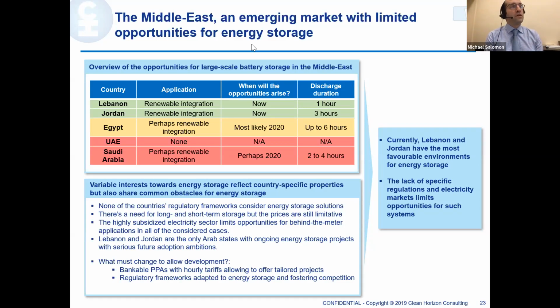So indeed, the sodium sulfur batteries I mentioned tend to work at higher temperatures, so one tends to see them as more fit for the region. But to be quite frank, lithium-ion batteries always come with HVAC, air conditioning, because you have to maintain them very strictly between 23 and 25 degrees Celsius - a very narrow temperature range. But what is the HVAC actually used for? It's usually to remove the excess heat generated by the batteries themselves.